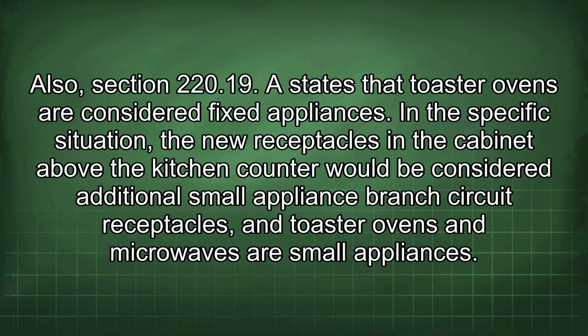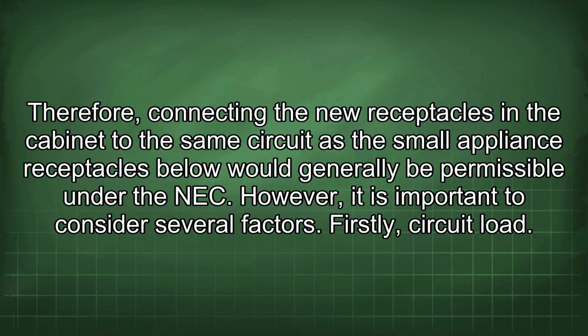In the specific situation, the new receptacles in the cabinet above the kitchen counter would be considered additional small appliance branch circuit receptacles, and toaster ovens and microwaves are small appliances. Therefore, connecting the new receptacles in the cabinet to the same circuit as the small appliance receptacles below would generally be permissible under the NEC. However, it is important to consider several factors.